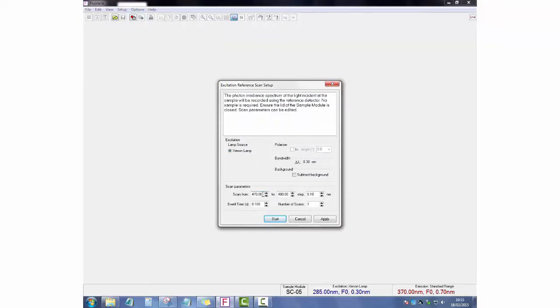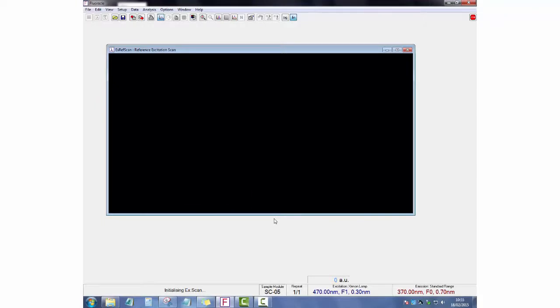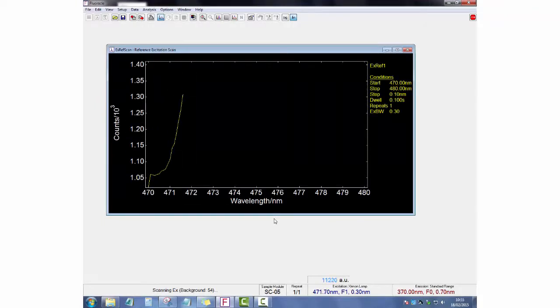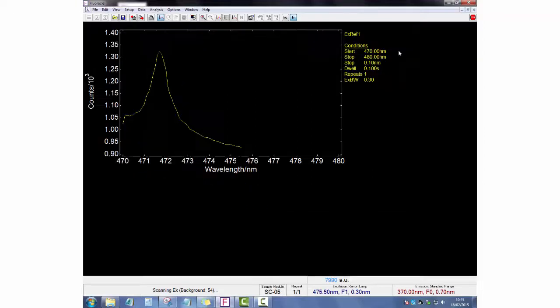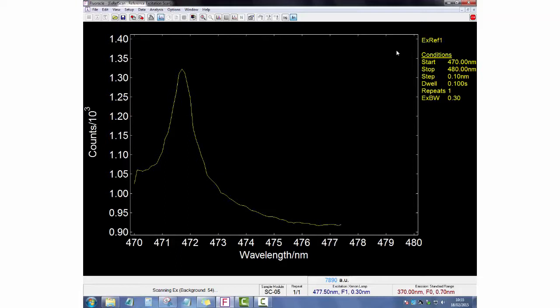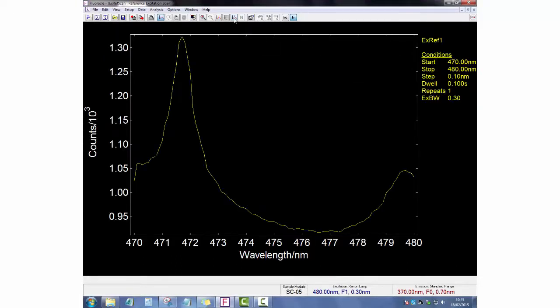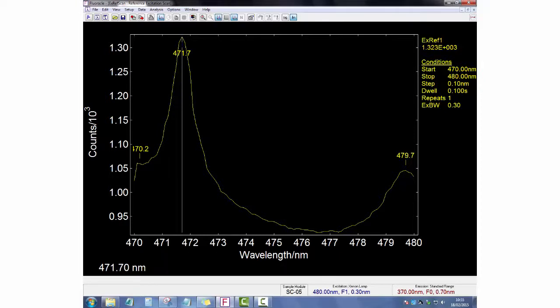We now scan over the spectral range of 470 nanometers to 480 nanometers, and we hope to see the xenon line coming in around 473.4 nanometers. In order to calibrate the excitation monochromator, we use the positions of the xenon lines, in particular the one at 473.4 nanometers. The monochromator should be kept within a calibration specification of plus or minus 0.5 nanometers.